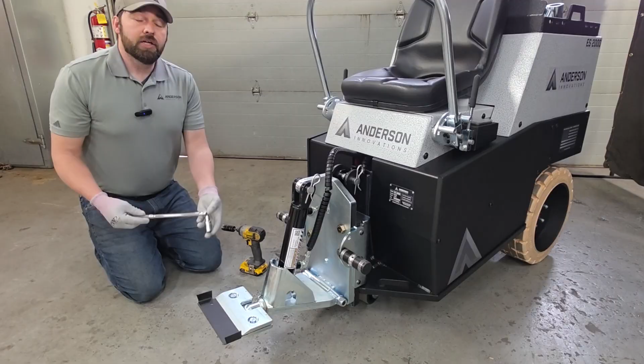An important note about using a wrench like this one to tighten the blade: when it's installed on the blade holder, you never want to push towards the cutting edge. It's very dangerous, as your hand could slip and come in contact with the sharp edge. If you're going to be using a hand wrench such as this one, we recommend that you put the handle away from the cutting edge so that as you're pushing, you're nowhere near this sharp edge. That's the safest way to install a blade with a manual wrench such as this one.